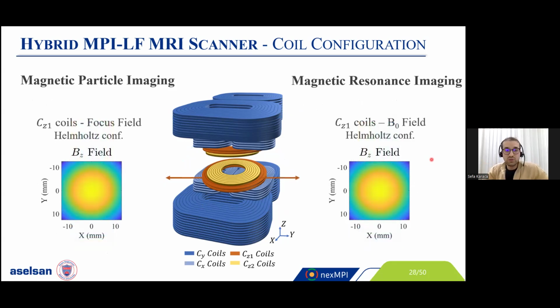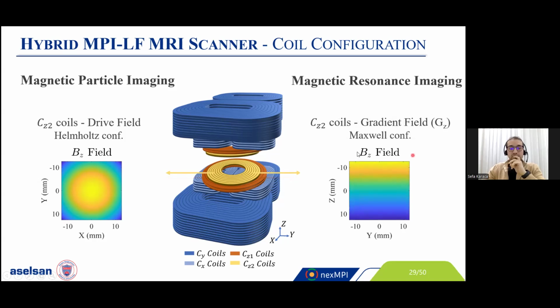And we have another coil group called the CZ1 coils. In the case of MPI, we use this coil group in the Helmholtz configuration in order to generate the homogeneous focus field of MPI. For MRI, we can use them again in the Helmholtz configuration to generate a homogeneous field, and we can use it as the main static field, or B0 field, of MRI. As a last coil group, we have the CZ2 coils. In MPI, we use them in the Helmholtz configuration again in order to generate the excitation, the drive field. This is a homogeneous field. But in the case of MRI, we can use them in the Maxwell configuration in order to generate a gradient field in the Z direction, which can be utilized as a spatial encoding gradient for MRI.